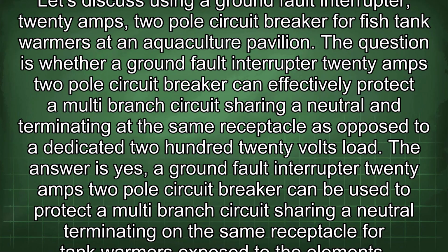Let's discuss using a ground fault interrupter, 20 amps, 2-pole circuit breaker for fish tank warmers at an aquaculture pavilion. The question is whether a ground fault interrupter 20 amps 2-pole circuit breaker can effectively protect a multi-branch circuit sharing a neutral and terminating at the same receptacle as opposed to a dedicated 220 volts load.